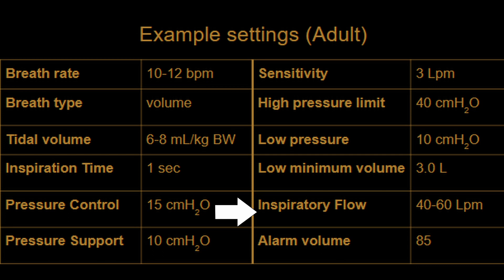This is different from the ventilator's positive end expiratory setting, which keeps the lungs slightly inflated at the end of each breath, preventing lung collapse. To summarize, here we show the settings suggested for adults by the LTV 1200 manual. Children and infants will need different settings. Consult your manual and a medical professional for your specific case.